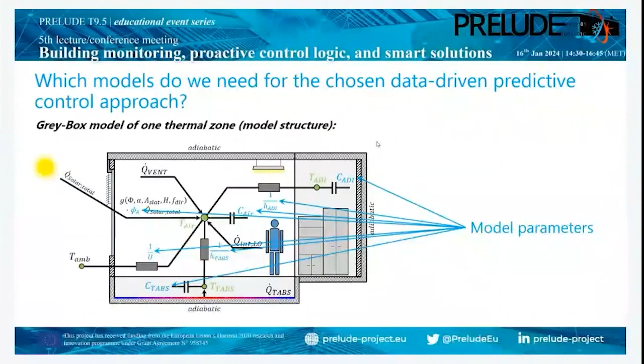We have direct and indirect measured values, and we also have the model parameters, shown in blue. As you can see, we have 7 parameters used for one thermal zone. Since we have 7 thermal zones, in total we need to identify 49 parameters for all thermal zones using the historical data.